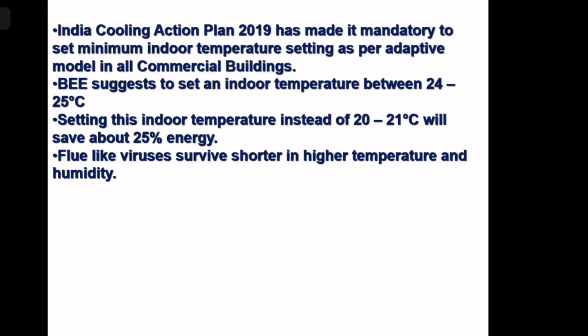Flu-like viruses also survive shorter in higher temperature and humidity. In fact, in the COVID situation, ISHRAE was suggesting that you set your AC temperature even higher than 25 degrees centigrade. You set it at 27, 28 and run the fan. Run the fan, so that if by chance any virus comes inside the room, that will also survive for a lesser period in that higher temperature.